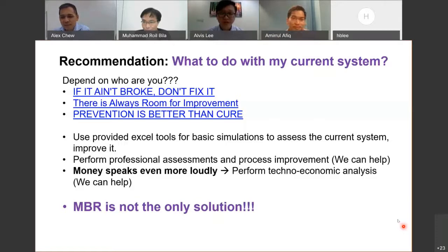Okay, Dr. Roy, I think there are last three questions here. The first one is from Miss Li Hui Ling. She is asking whether using MBR can help reduce the hardness in treated effluent for reuse purposes. The answer is no. We cannot, because calcium and magnesium are in solution, and they are so small they will pass through the membrane pores.